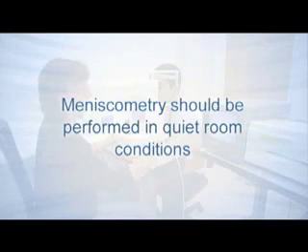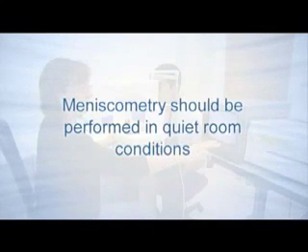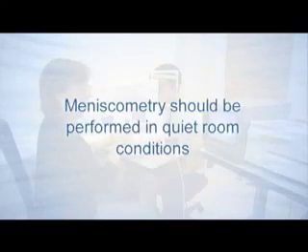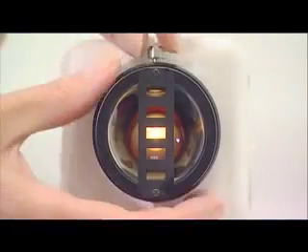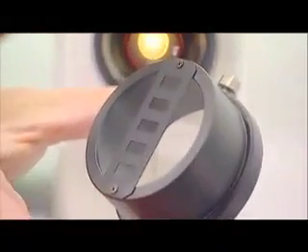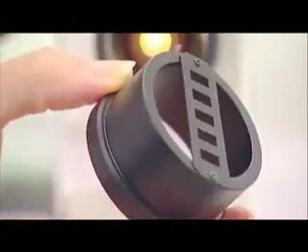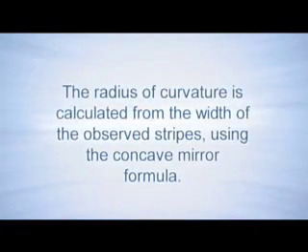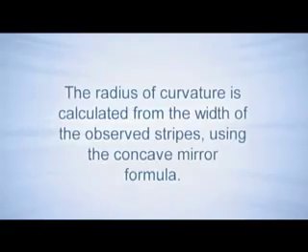Meniscometry should be performed in quiet room conditions. With this technique, an illuminated black and white horizontally striped target is projected onto the lower central tear meniscus, and the real-time reflected image is viewed coaxially and captured for analysis. The radius of curvature is calculated from the width of the observed stripes using the concave mirror formula.